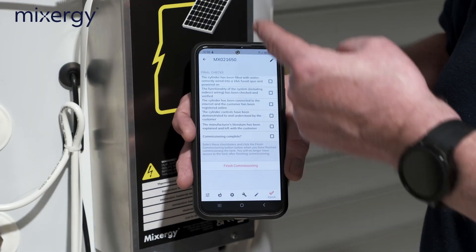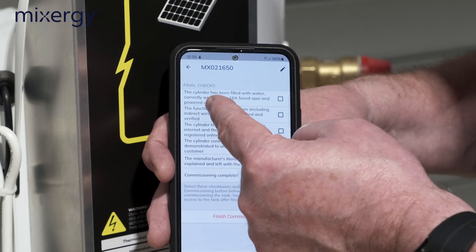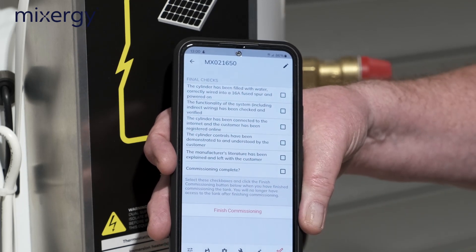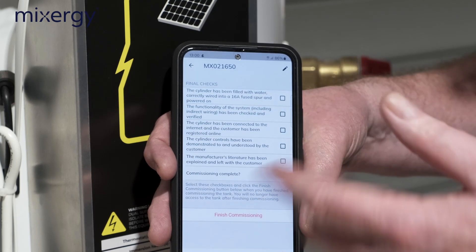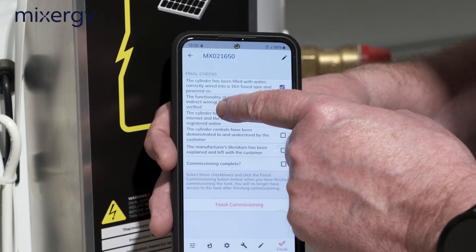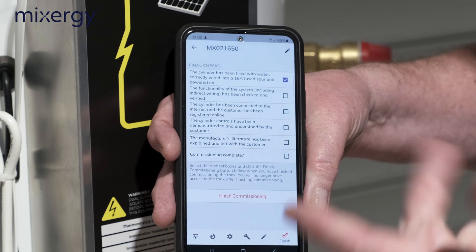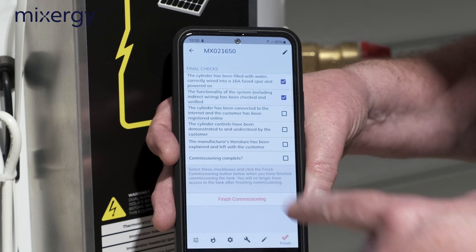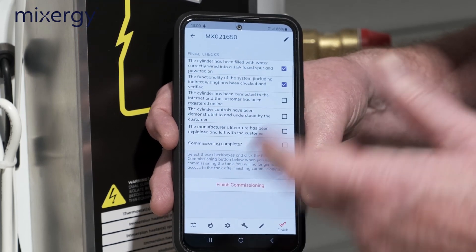Finally, we fill in the commissioning checklist. 'Cylinder has been filled with water, correctly wired, and has a 16-amp fuse spur powered on' — we generally use a 16-amp MCB with a 20-amp double-pole isolating switch, so tick that one. 'Function of the system including indirect wiring has been tested' — we've checked the heat pump or boiler and the immersion heater, so tick that.